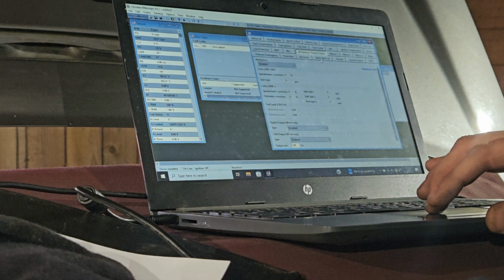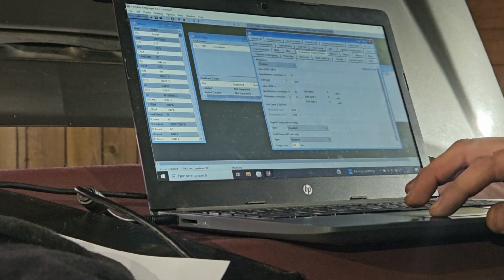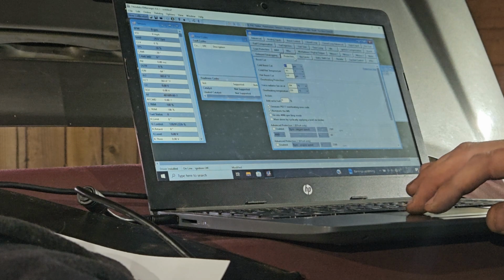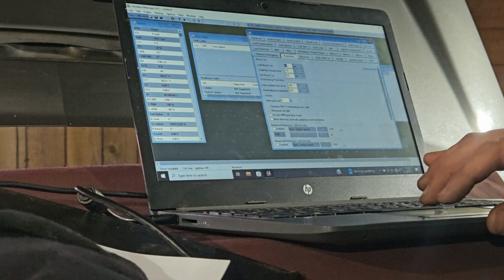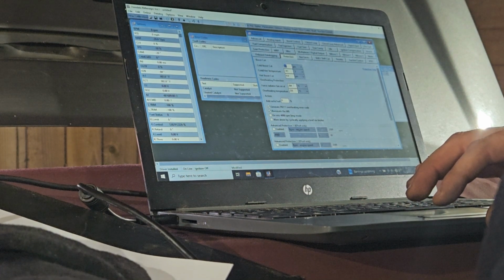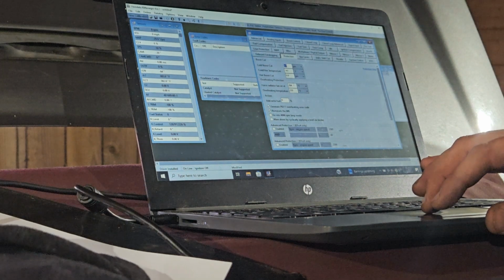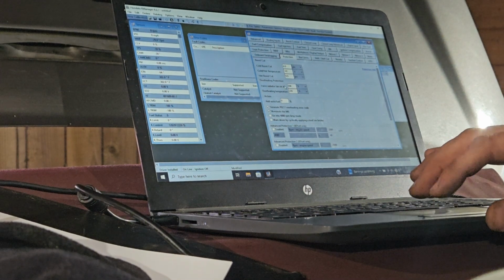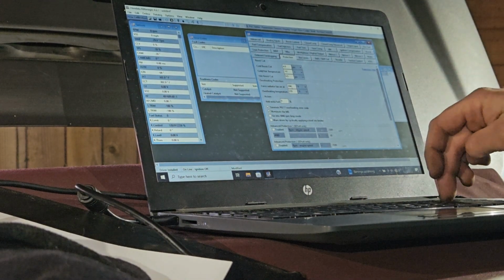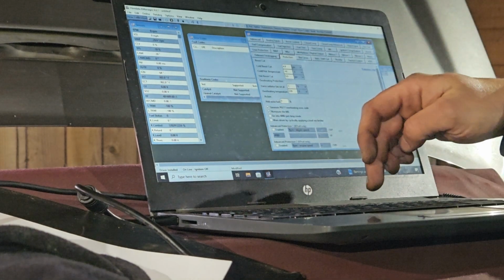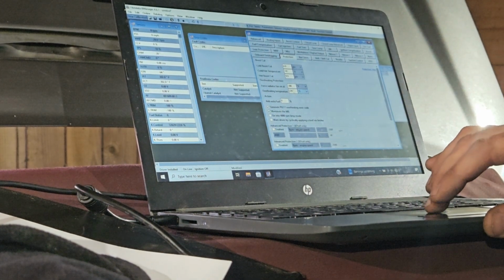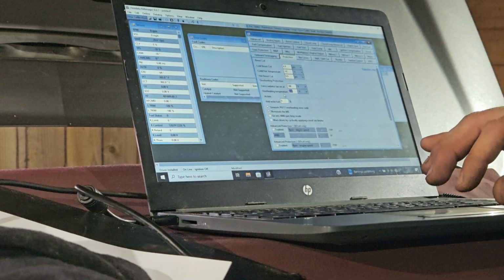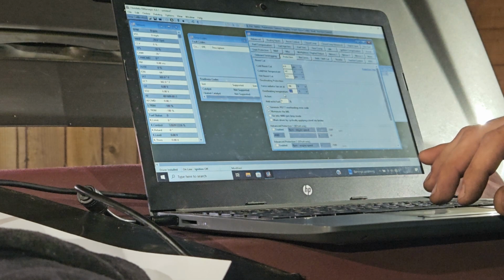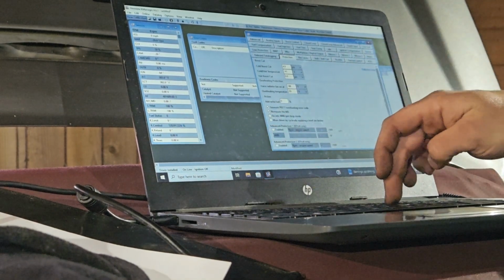This is under protection, isn't it? So, protection - overheating fans. This has to be set at overheating, one fan, radial fan. It says between 180 and 185, so we're going to do 180. Overheating temperature error code, we don't want it to go above 205.